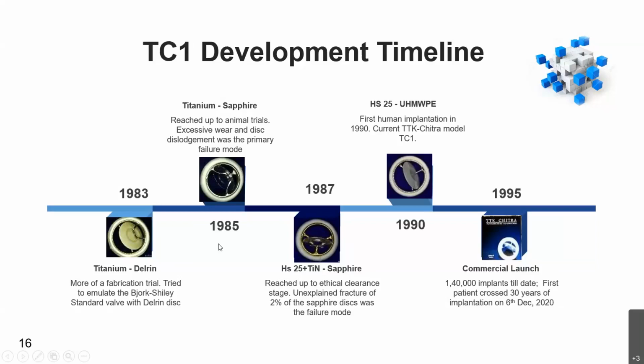So what we found in the case of this first model is that this particular device will fail after about 200 to 300 million cycles, and that corresponds to about 4 to 5 years or maximum 6 years of life inside the patient, and this was not acceptable to us. So we started looking for alternate materials, and within 2 years we had a new model in which the titanium in the first model was replaced by a cobalt-based alloy, Haynes 25, and it had a coating of titanium nitride. And this titanium nitride is a ceramic and is supposed to have extremely good blood compatibility and biocompatibility. And these are the two mandatory criteria for all materials which are used in medical implants.